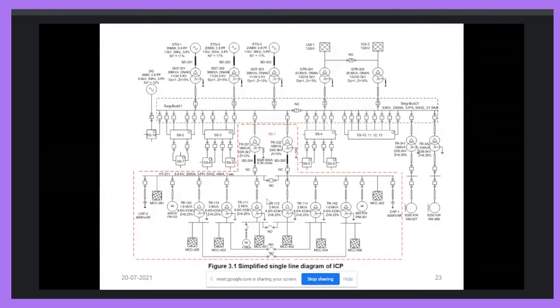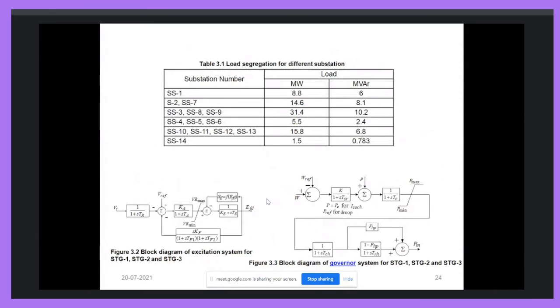There you can see there is a transformer and load. So this is basically the industrial system on which the designed load shedding is tested, or you can say we will see how we can design the load shedding for this system. Here the loads of the different substations are represented.